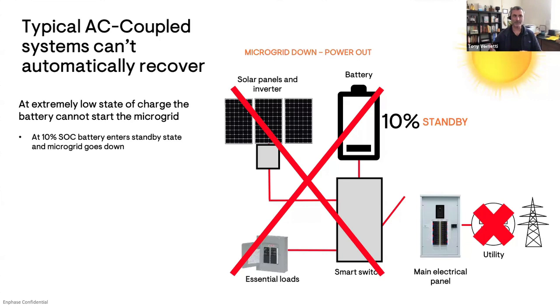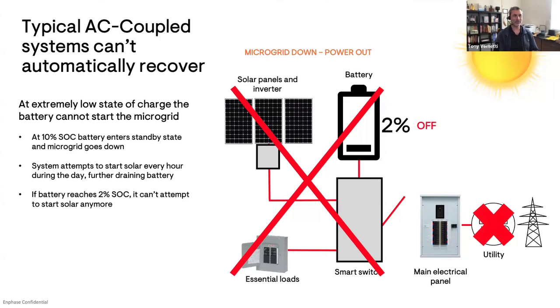Now, this happens because in typical AC coupled systems, the solar inverters need the battery to be there to form the microgrid. That allows them to turn on and start converting power. The system doesn't know when solar power is going to be available, when the sun's going to come out again. So it needs to keep some energy in reserve so it's able to try to start solar the next day. During the day, the battery is going to keep powering up and seeing if the solar system is actually working. Every time it does that, it consumes energy. Eventually, it's going to drop down to 2%, which is an extremely low state of charge. And the battery is basically going to stay off at that point until the utility grid is back up again.